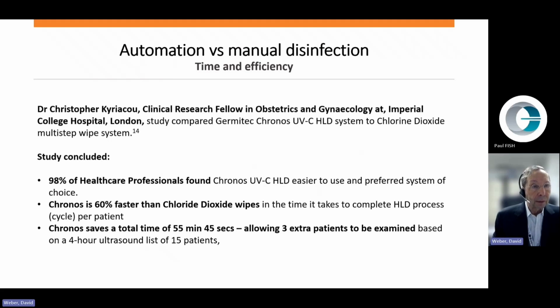Let's turn now to time and efficiency. One colleague, a clinical research fellow in obstetrics and gynecology at Imperial College Hospital, London, conducted a study comparing Germitec Chronos UVC high-level disinfection to a chlorine dioxide multi-step wipe system. The study concluded 98% of healthcare professionals found the Chronos UVC high-level disinfection easy to use and the preferred system of choice. Further, Chronos is 60% faster than chlorine dioxide wipes in the time it takes to complete HLD processes, that is cycles, per patient.